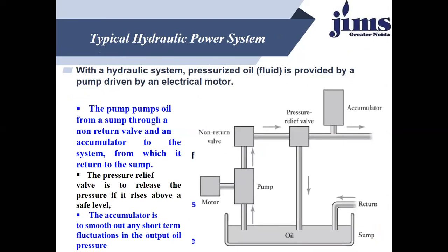See this diagram. I already discussed how it works. In the hydraulic system, pressurized oil is provided by a pump, which is driven by an electric motor. So the pump must be run by the electric supply. What is the function of the pump? The pump draws oil from the sump. The sump is the reservoir. The pump will pump the oil from the sump through a non-return valve, which cannot return itself, and an accumulator, which I already told you about, to the system, from which it returns to the sump.